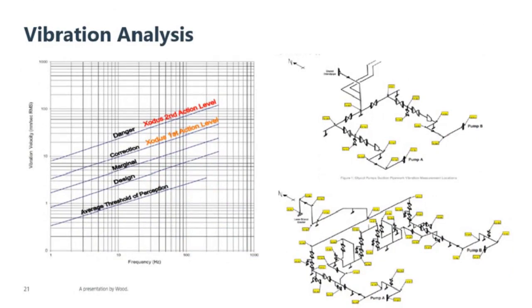And in early days, more common vibration analysis was used, with a handheld accelerometer and a recorder. That basically mapped the pipework, and it gave a better understanding of where there was a continuous risk of weld fatigue failures. After that initial integrity concern, some attention was put onto the system, and then the vibrations were low enough that it wasn't an integrity risk. However, the pump reliability was still a problem, and that's why the motion amplification study was done.